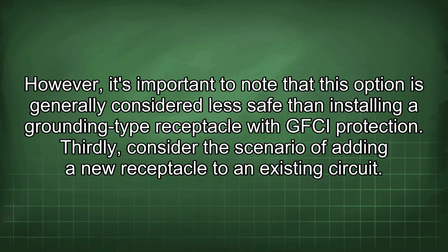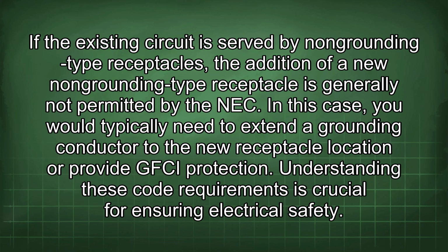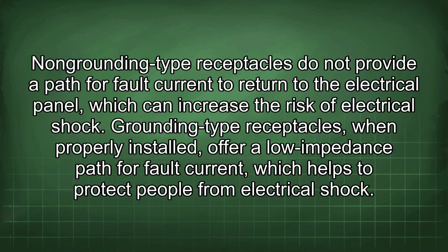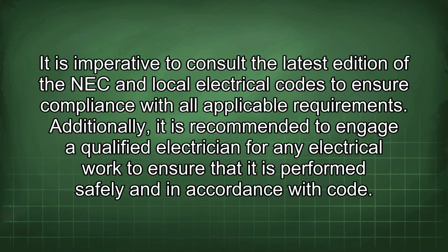Thirdly, consider the scenario of adding a new receptacle to an existing circuit. If the existing circuit is served by non-grounding type receptacles, the addition of a new non-grounding type receptacle is generally not permitted by the NEC. In this case, you would typically need to extend a grounding conductor to the new receptacle location or provide GFCI protection. Understanding these code requirements is crucial for ensuring electrical safety. Non-grounding type receptacles do not provide a path for fault current to return to the electrical panel, which can increase the risk of electrical shock. Grounding type receptacles, when properly installed, offer a low impedance path for fault current, which helps to protect people from electrical shock. It is imperative to consult the latest edition of the NEC and local electrical codes to ensure compliance with all applicable requirements. Additionally, it is recommended to engage a qualified electrician for any electrical work to ensure that it is performed safely and in accordance with code.